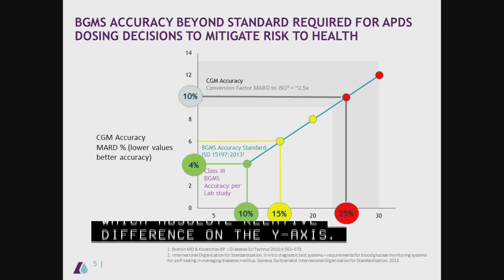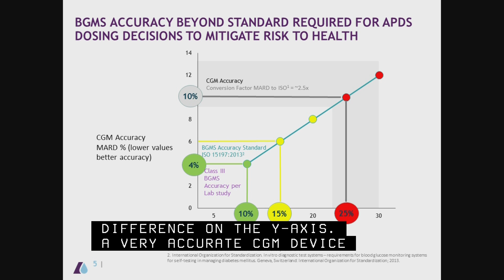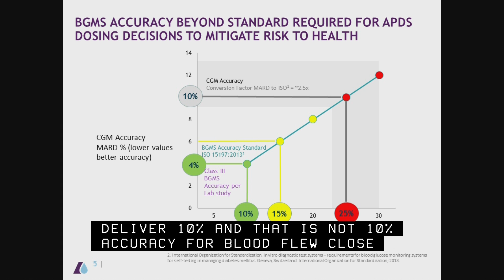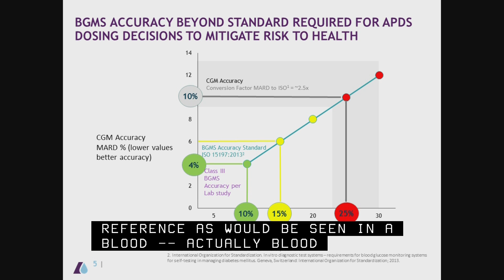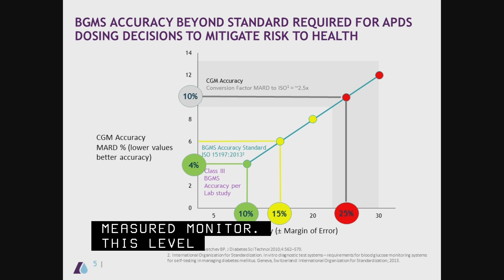So today, a very accurate CGM device would deliver a 10% MARD, and that does not correspond to a 10% accuracy for blood glucose monitoring. In fact, that corresponds more to a plus or minus 25% to a lab reference, as would be seen in a blood glucose measured monitor. This level of plus or minus 25% is kind of reflective of levels that we've seen back in the 90s, right? So it's evolving technology, getting much better, but still not as accurate as a finger stick.